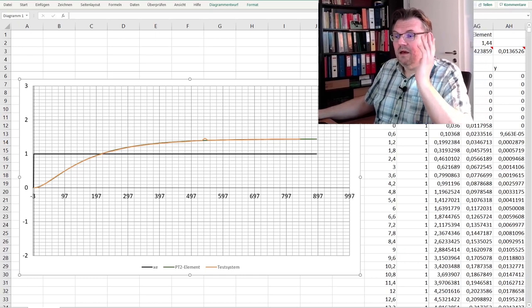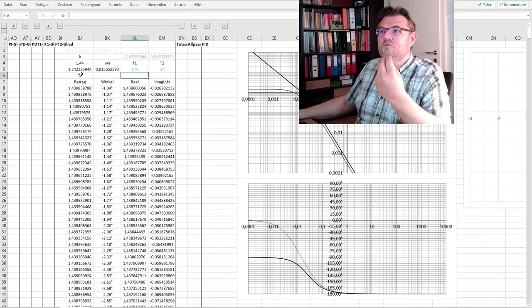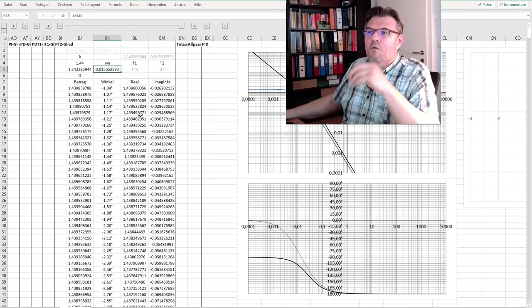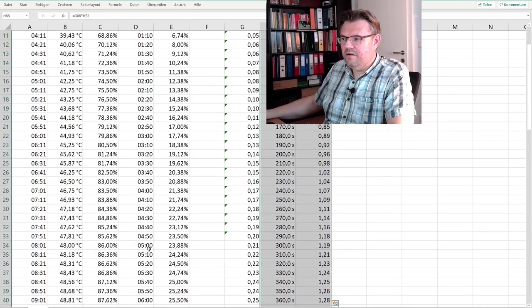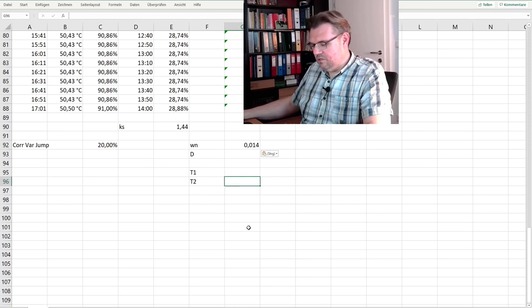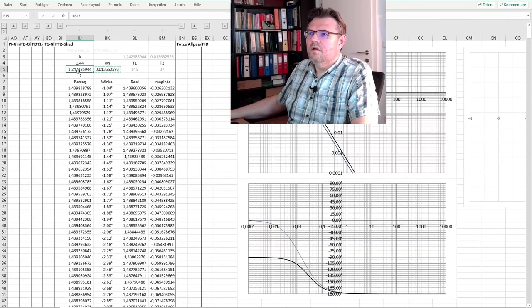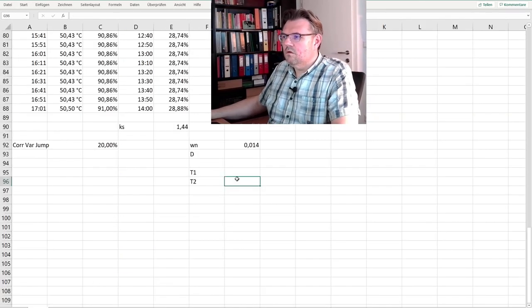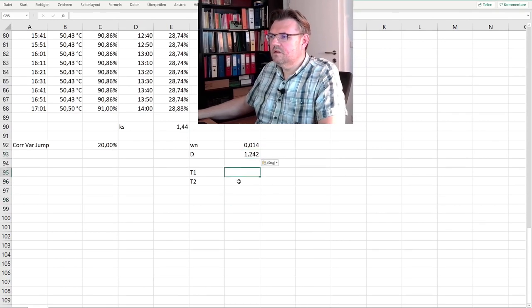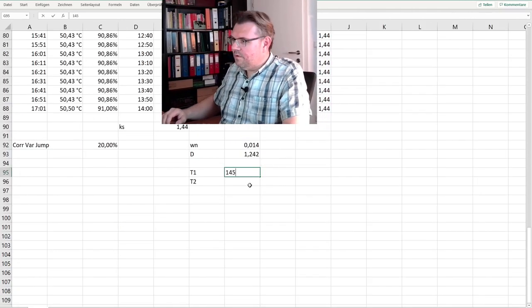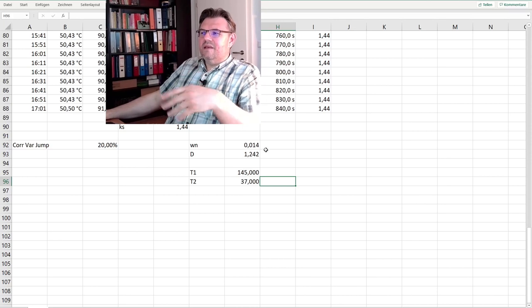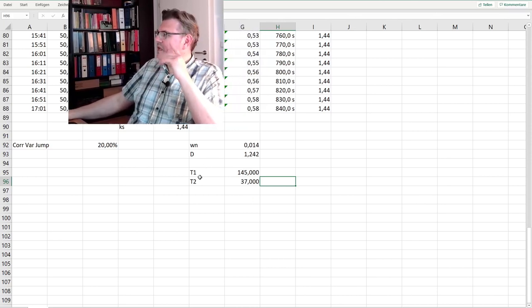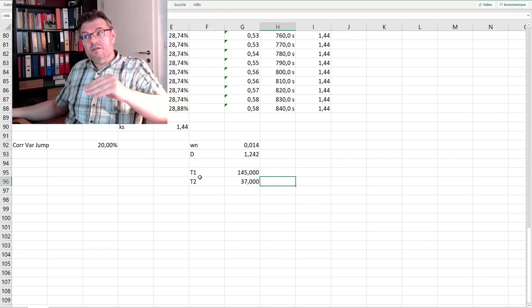What does it mean? I have now calculated the parameters of the PT2 system. Our natural frequency is this, I will copy this and write it here in our analysis tab. Our natural frequency is 0.014, this is our damping factor 1.24, and T1 and T2 was 145 and 37. It's just redundancy because T1 and T2 I can calculate to omega n and T. This is my system.